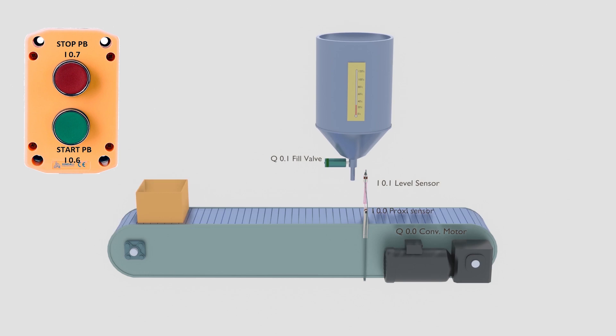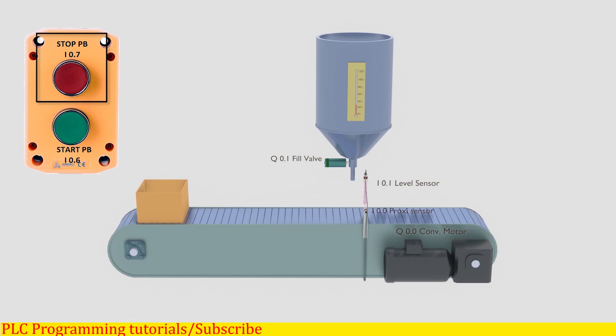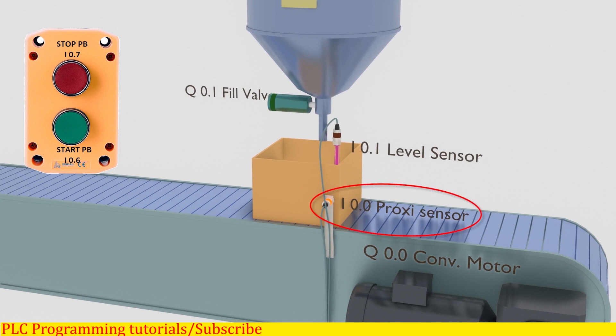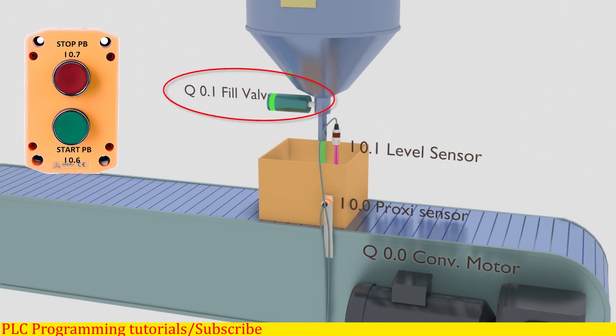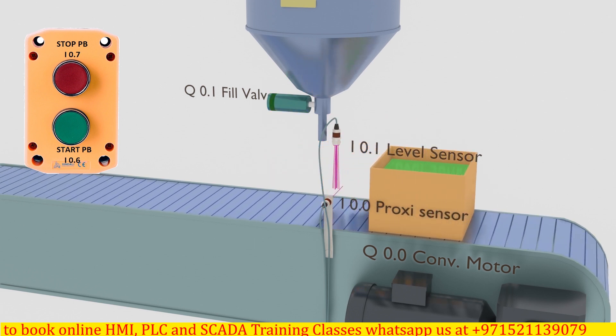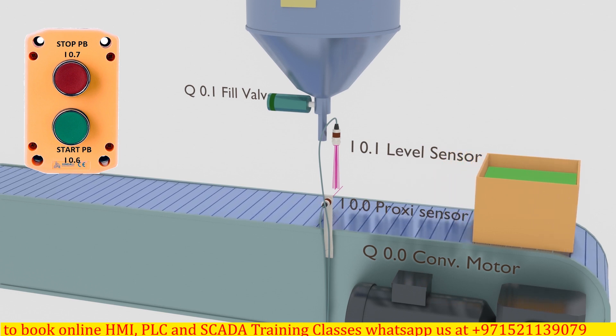Today we have a box filler machine to program. This machine starts the process with the start push button I 0.6 and stops with the push button I 0.7. It has a conveyor to transport the box, which runs with PLC output Q 0.0. Box presence at the filling station is confirmed by the box sensor I 0.0. Once the box is at the filling station, the filling valve Q 0.1 opens and starts filling liquid into the box. Once the box is filled, the fill level is confirmed by the level sensor I 0.1. The filling valve closes and the conveyor starts again to remove the filled box and bring in the next empty box under the filling nozzle.